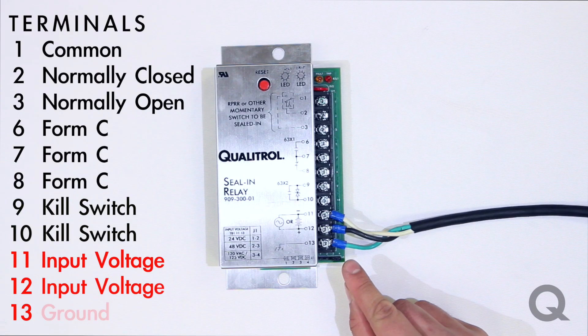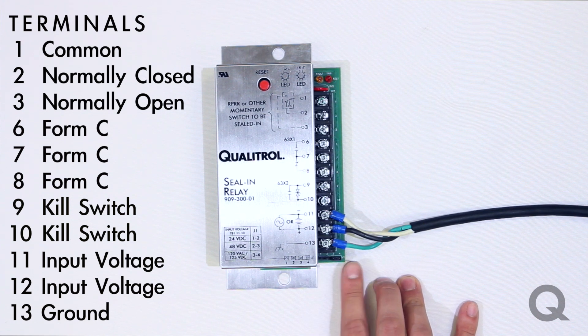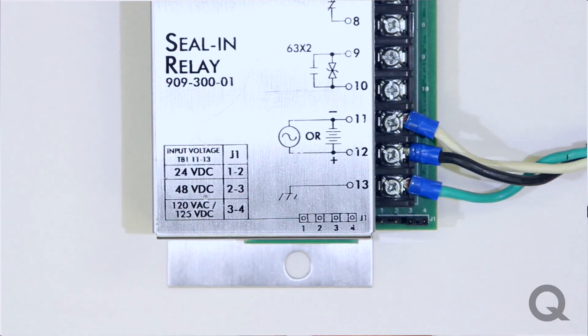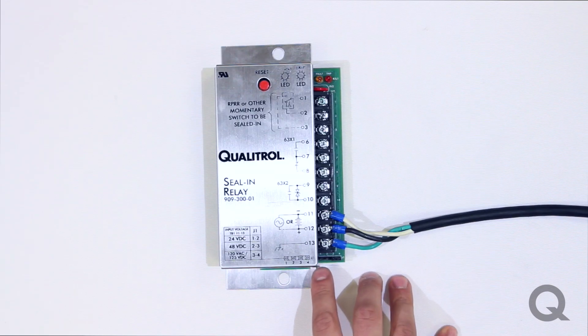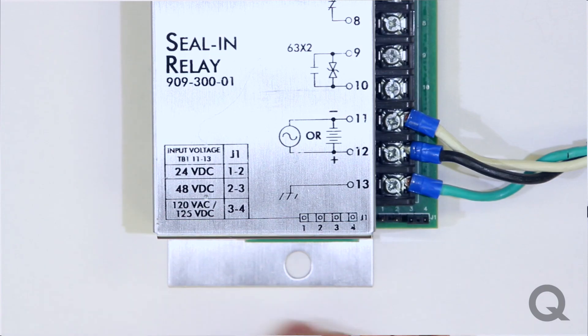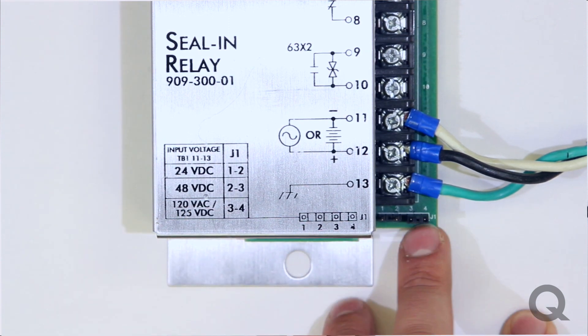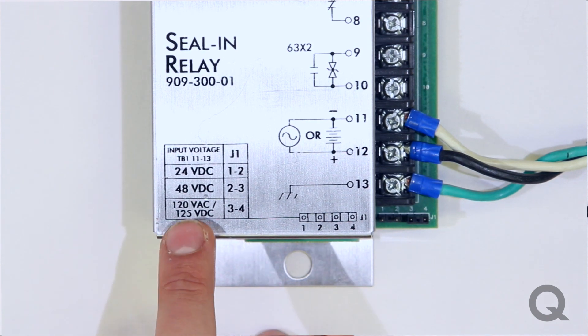Terminals 11 through 12 are your input voltage and terminal 13 you would use for ground. Below these terminals you have your jumpers for different voltages that you can select. On the seal-in relay itself you see a table listing the different voltage patterns: on jumpers 1 and 2 you'll be running at 24 volts DC, on jumpers 2 and 3 you'll be running at 48 volts DC, and on jumpers 3 and 4 you'll be running either 120 volts AC or 125 volts DC.